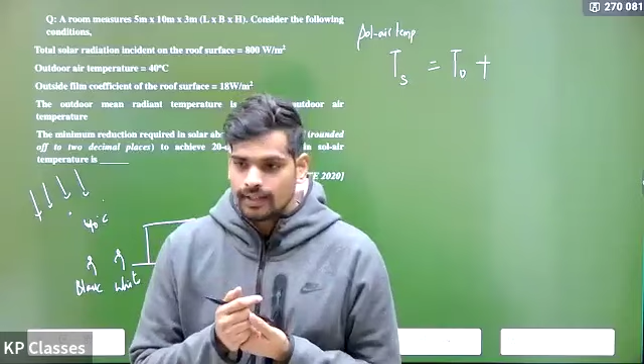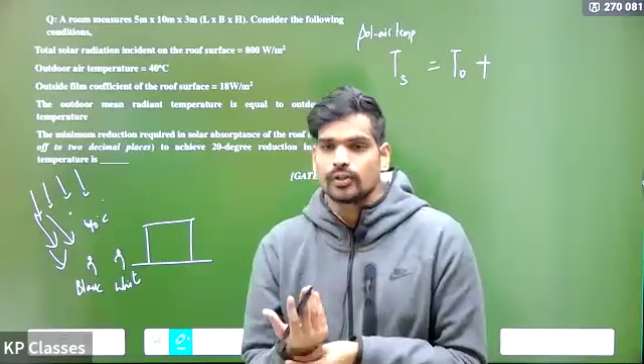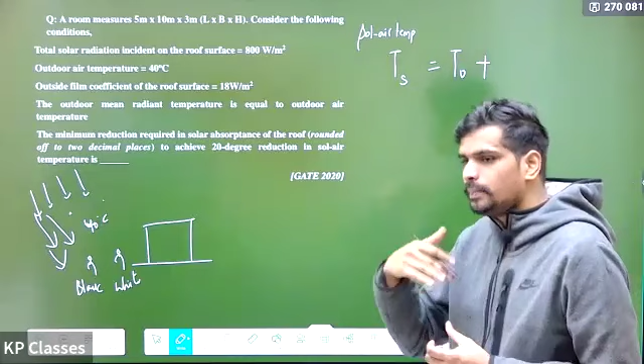So this is applied in architecture also. If there's a building with a dark exterior color, it will absorb radiation. That will increase the external temperature, the actual performance or actual consideration. So sol-air temperature is outdoor air temperature plus an extra value. That extra value depends on the absorbance. It depends on the intensity of the incident solar radiation into absorbance upon surface conductance.